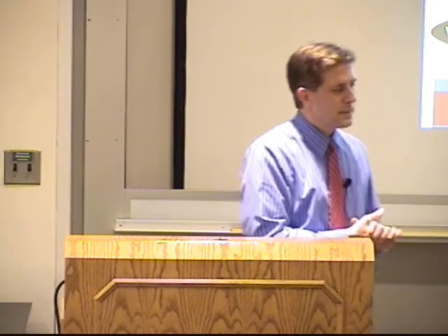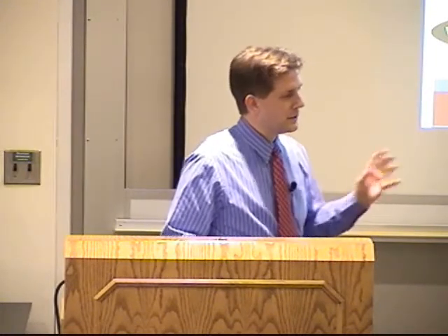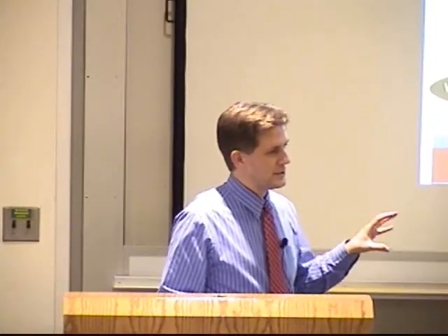Yes. Just a follow-up on the previous question. It sounded like the Fourier transform was the bottleneck for the first algorithm, the OCT. Is it also the bottleneck for the ISAM? Yeah, so everything we have to do for ISAM, we have to first do for OCT. So ISAM is essentially OCT, but keeping better track of the phase information of the light and oversampling in OCT, and then using that oversampling to reconstruct the ISAM image. So there's just another level of processing that has to go on for the ISAM.